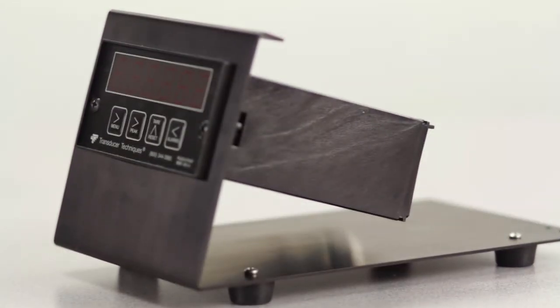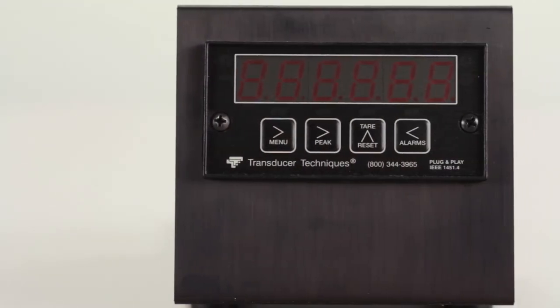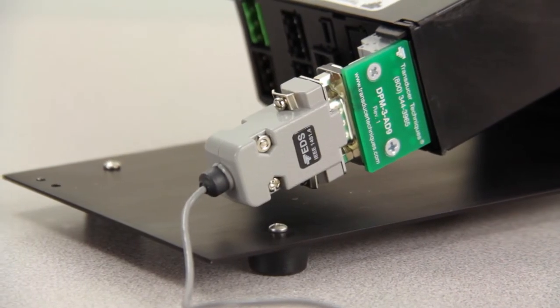This is our DPM3, which is a smart plug-and-play IEEE 1451.4 compliant meter. One of the great features using the plug-and-play system is when you plug a load cell into the DPM3, the first thing it does is read the EEPROM in the load cell.